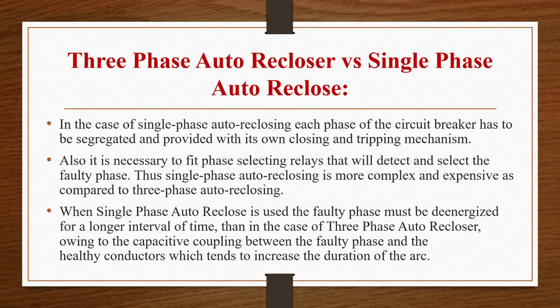So in case of single phase auto reclosing, each phase of the circuit breaker has to be segregated and provided with its own closing and tripping mechanism. It is also necessary to fit phase selecting relays that will detect and select the faulty phase. Such single phase auto reclosing is more complex and expensive as compared to three phase auto reclosing.